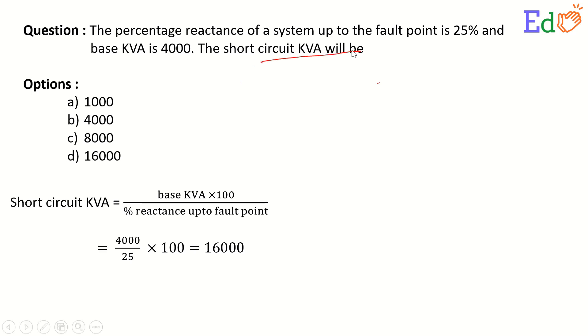there is a formula readily available: base KVA times 100 divided by percentage reactance up to the fault point. As given, 4000 is the base KVA, percentage is 25, and multiplied by 100 it gives 16000.